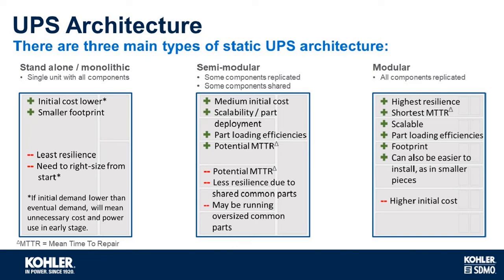But with the true modular, we consider this the highest resilience, typically the highest availability, because everything is modular and it should be hot swappable. You'll have the shortest mean time to repair on the site. Very scalable. You put in what you need, and that can be changed around as you change the load either up or down. And because of the efficiencies, the part load efficiencies are extremely good. So on low load, it's very good. And if you need to take some out, you can take that out and make sure you're running it in the most efficient case. Typically with these true modular UPSs, the footprint is very good. They can be dismantled and put into tighter, smaller spaces. But all that comes at a slightly increased cost over probably the standalone or things like that.